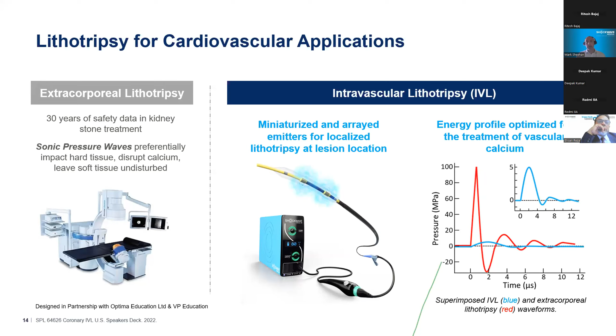So everybody will be very familiar with the kit for Shockwave. You have the generator and the connector cable, which are obviously reusable and not to be disposed after the case. And then obviously the single-use catheter, which for coronary is the C2 catheter, comes in sizes 2.5, 3.0, 3.5, and 4.0. The working length of the balloon is always 12 millimeters.